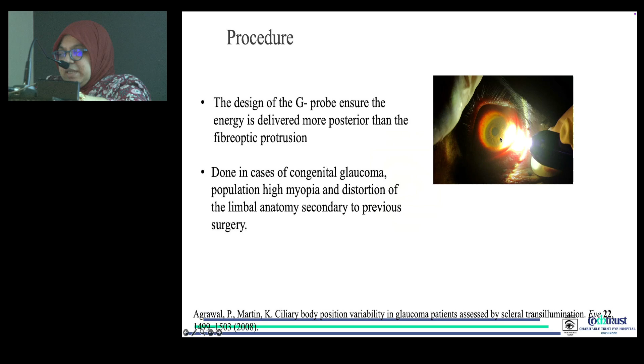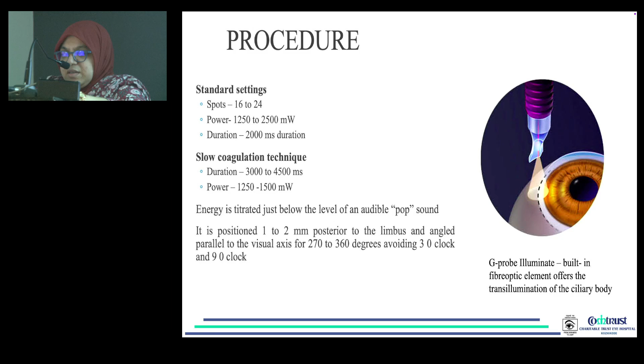There are two settings where we can do the procedure. One is the standard setting: the spot size is about 16 to 24, the power is 1250 to 2500 milliwatt, and the duration is 2000 milliseconds. Then there is the slow coagulation technique, where the duration is about 3000 to 4000 milliseconds and power is 1250 to 1500, and energy is titrated just below the level of an audible pop. It is positioned 1 to 2 millimeter posterior to the limbus and angled parallel to the visual axis, avoiding the 3 o'clock and 9 o'clock positions. The G-probe Illuminate has an inbuilt transillumination for the ciliary body.